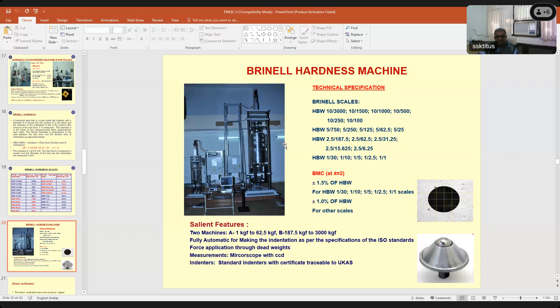Okay, now how to verify these machines? This is very, very important. We just saw how the hardness scale is achieved, how hardness measurement is done, and what the requirements are. Now you are very much clear. You need an indenter, you need an application of force, and you need to measure the indentation depth, or the diagonal, or the diameter of the indentation made by the indenter.